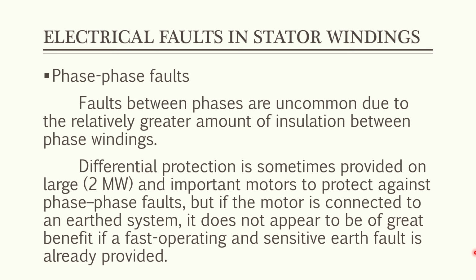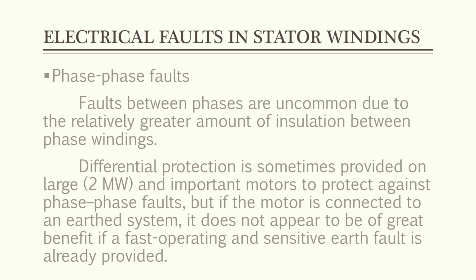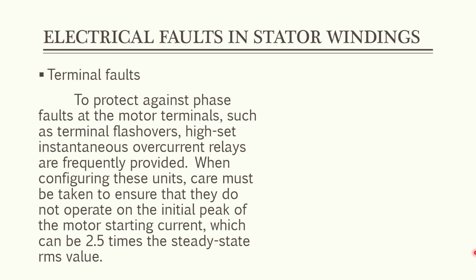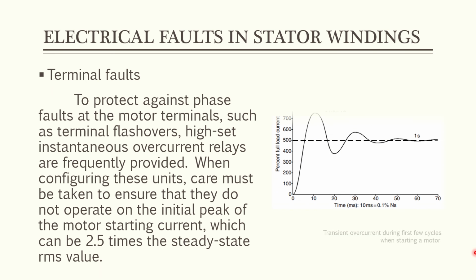Differential protection is sometimes provided on large and important motors to protect against phase-to-phase faults. But if the motor is connected to an unearthed system, it does not appear to be of great benefit if a fast operating and sensitive earth fault protection is already provided. Terminal faults. To protect against phase faults at the motor terminals such as terminal flashovers, high-set instantaneous overcurrent relays are frequently provided. When configuring these units, care must be taken to ensure that they do not operate in the initial peak of the motor starting current, which can be 2.5 times the steady-state RMS value.